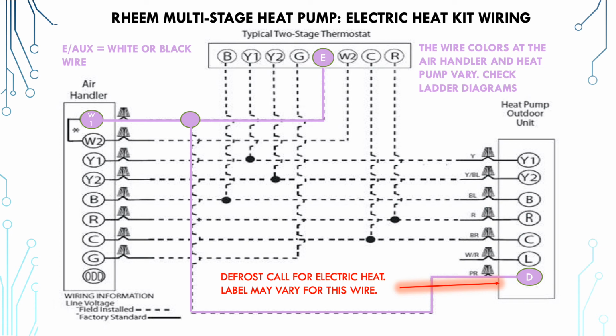So you have multiple means of turning on the electrical heat. Now, the thermostat should have a functionality of isolating and selecting emergency heat in case something is wrong with the outdoor heat pump. The Nest can do it, but it's a little more complicated, and most of the time customers can't figure it out. So Nest is not always the most ideal thermostat with heat pump configurations. However, it is a functionality that's possible.